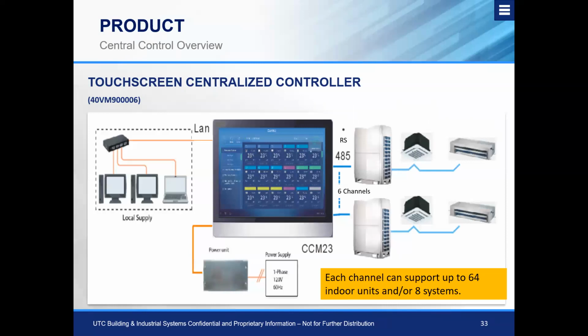Now on this touchscreen controller as well, you can see here, it takes all the information from our outdoor units and broadcasts to the central control. We require a 120 volt power supply. So typically where you're locating this, you'd want this by a power outlet to plug in. And then of course we have the ability on here to customize the IP addresses to match whatever your on-site IP address is, to send out to a modem so that you can remotely monitor via IP address to log into the system at a local supply, or you can also set it over Wi-Fi so that you can log in and see the system at any given time, to be able to see if there's an error, to make changes, or just to inquire about the units to see how they're performing.